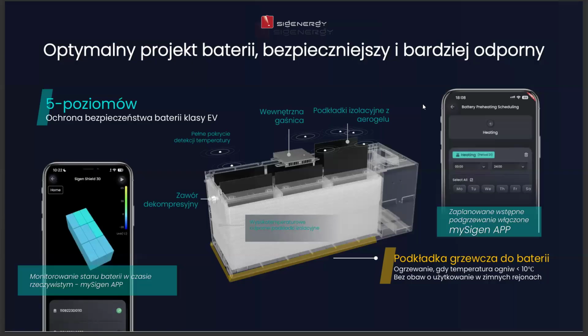For us, outdoor installation is not a marketing claim, it is a real engineering capability. Each battery module includes a built-in heating mat, 200W or 300W, and full thermal insulation on all sides. In freezing conditions around -15 degrees Celsius to -20 degrees Celsius, a system with 6 modules uses approximately 2 kWh per day only for heating. This keeps the battery operating within the optimal temperature range, preserving both performance and service life, even when installed outdoors.